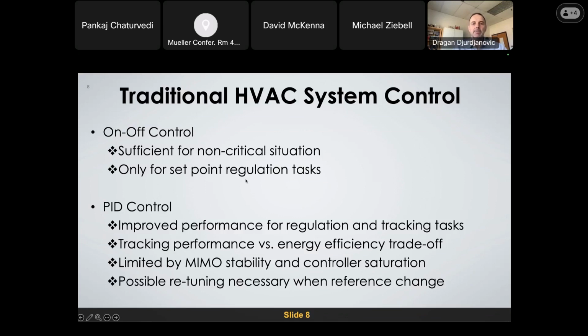So traditional HVAC systems rely on relatively basic control methodologies, on-off control and PID control, which really don't require a lot of computation, because the task is usually relatively simple. You're trying to keep a constant temperature, and anytime you deviate from that temperature, you switch the flow on or off. With PID control, the on-off switching is smoothed.